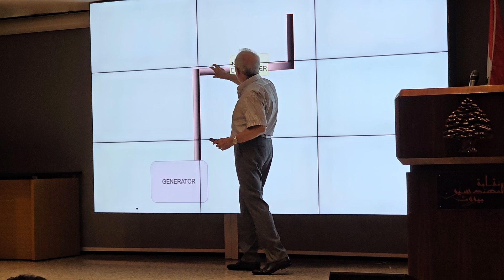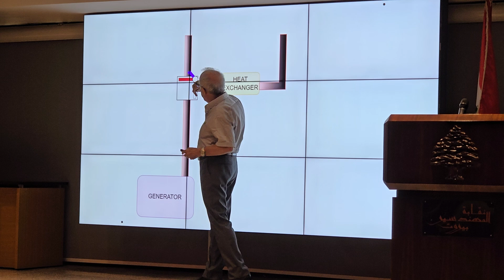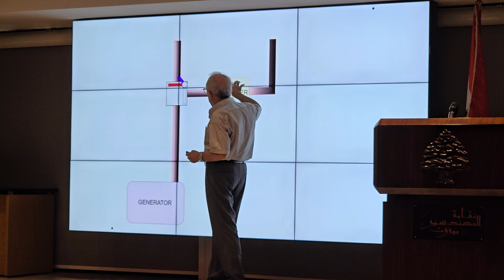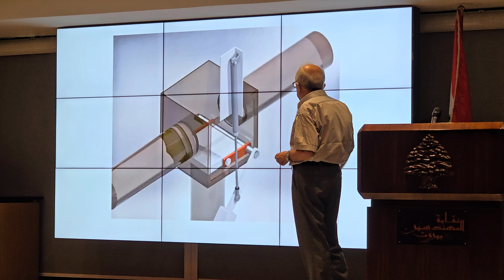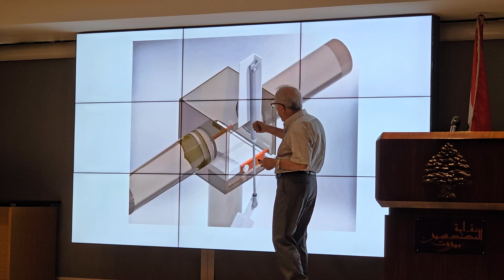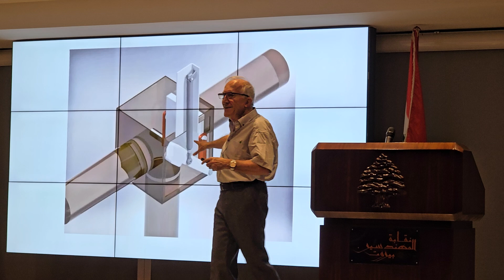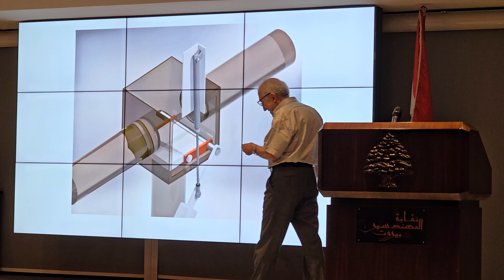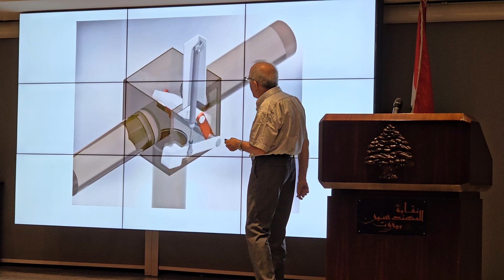The generator, how do we do it? The generator has the fumes, they go into the heat exchanger, and this is where we recover the heat. If we are not recovering the heat fully, we are obliged to put here a diverter. In case we are not recovering the heat, the diverter will open to the outside. The diverter has a double hinge to be very tight. I do this instead of playing cards. So this is how it works, and it is really very efficient because it has 2 hinges.